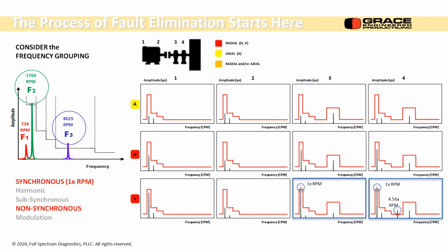You're going to pick it up when you use these online transducers. So you'll probably have to have a secondary stream of information telling you what the frequency was on the drive, and basically what speed it's rotating at every time. Otherwise, it's a little hard. You'll get two trends out of it, or multiple trends out of it, I would think.